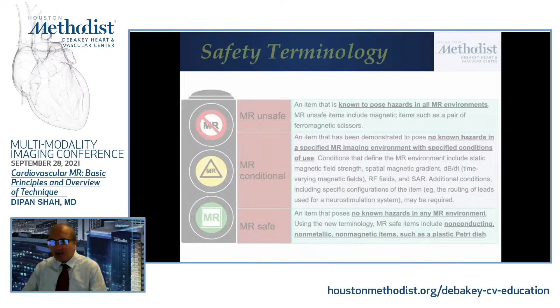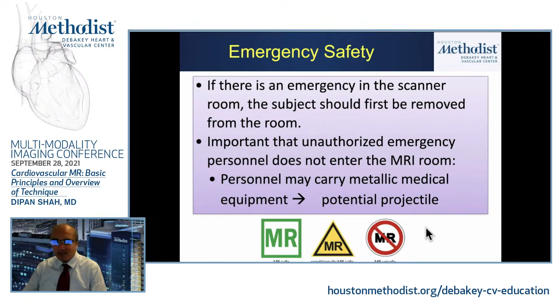This is very, very important, because otherwise what happens is you call a code and you start trying to do something, and obviously the equipment in the MRI room itself has all been checked to be MRI safe or MRI conditional. But what you don't know is that when the code team comes in with a bunch of supplies, those supplies are generally not going to be MRI safe or MRI conditional. Somebody, trying to do good to help the patient, could actually end up harming or killing the patient. So the most important thing is to pull the patient out of the room, close the door, and then begin your resuscitation effort. Again, this is a little bit counterintuitive to what we're used to, which is to attend to the patient and try to perform resuscitation immediately. But this is very, very important, and you have to get this ingrained into your head.